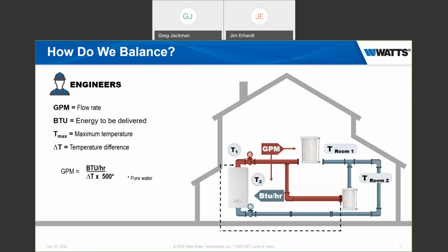But the average rule of thumb is about a 20-degree delta T. And finally, 500 is a constant. That's the heat carrying capacity of pure water. So what will happen in most commercial applications, and especially if it's a specified job, each heat emitter or cooling emitter or each fan coil or each chilled beam will have a specified flow rate that it needs to receive to maintain optimum operating efficiency and to keep the occupants comfortable. And that's all based again on the load. And if we don't supply enough flow, then we don't supply enough capacity, either heating or cooling, for that fan coil or whatever it is to do what it needs to do.